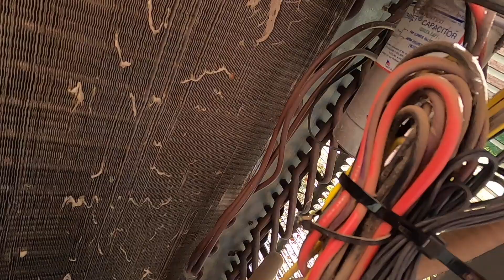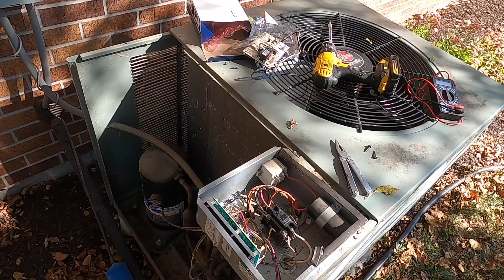And then the coil sensor, you can see it up in there. I can't tell if you can see it on the camera or not, but it's up in there. A little hard to get to without taking stuff off, but I managed to get it up there swapped out with the old one. And so we're gonna put this back together. We're gonna put the power back on. There's a 5-minute timeout cycle on the compressor. So after 5 minutes or so, we'll test the whole system out again, make sure we're not still getting heat coming on while the air conditioner's running.